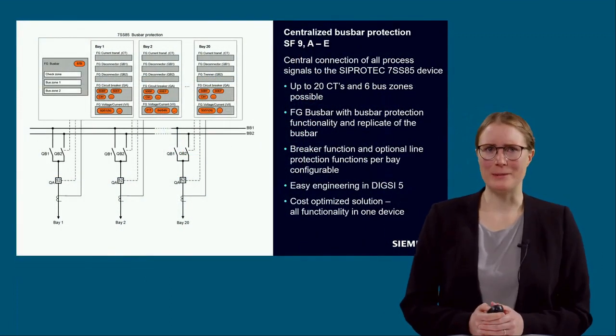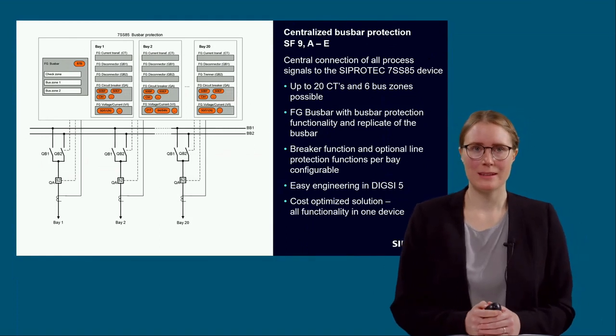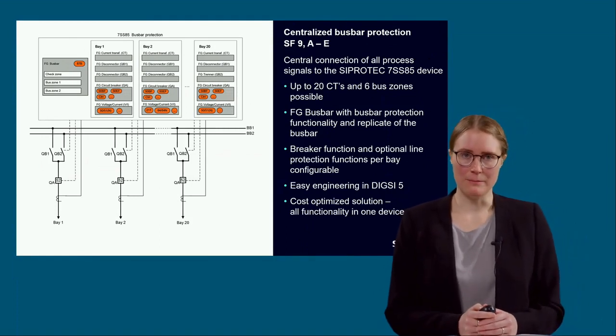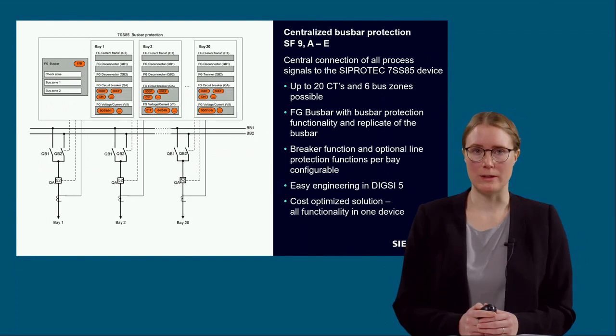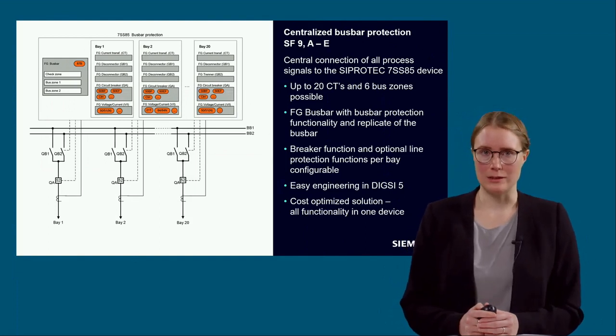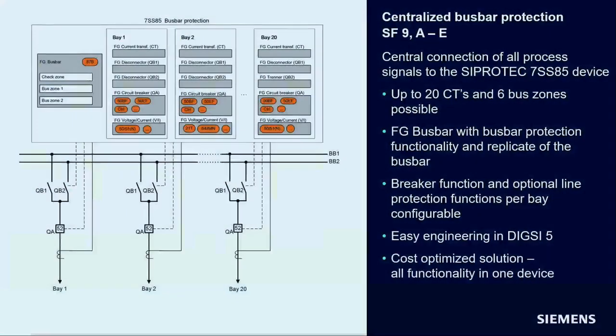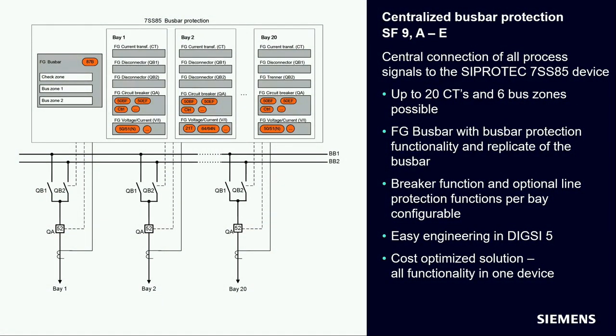Now I want to dive a little bit deeper into each solution. This slide shows a single line diagram of a double busbar system with 20 bays. In this sketch, only 3 of them are drawn as an example. Typically, for the centralized approach, the signals of the bays, that means the 2 disconnectors, the circuit breaker, and the current transformer, are directly connected to the 7SS85. Of course, enough current inputs must be available in the device. So with up to 20 bays, the device is a big one.